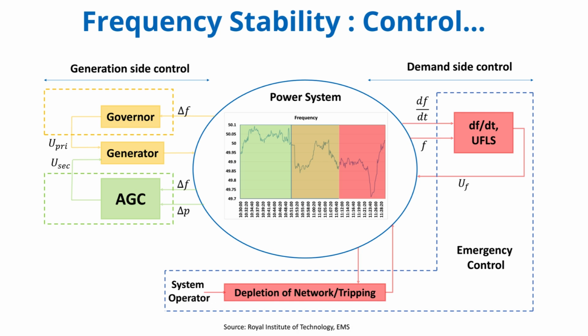frequency deviation quickly. And the emergency controls are there too, UFLS, under frequency load shedding. The last line of defense if frequency drops too low, automatically trips load in stages. And implicitly OFGS, over frequency generation shedding, if it goes too high. Yes, if frequency skyrockets due to, say, a massive loss of load, tripping some generation might be necessary. The goal is always to prevent a total frequency collapse or runaway. And the material rightly notes frequency control involves both generation actions and, increasingly, demand-side actions, like controlling flexible loads.